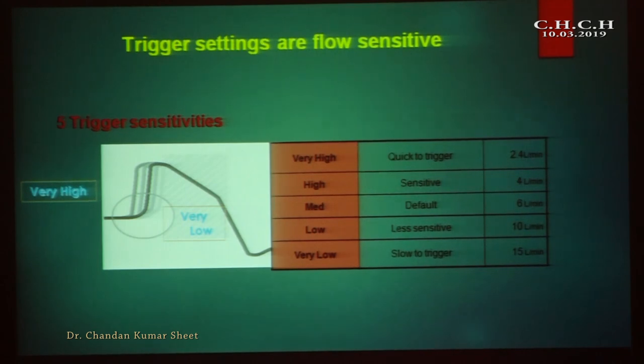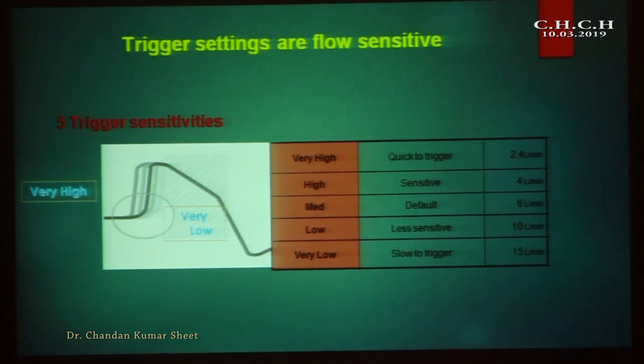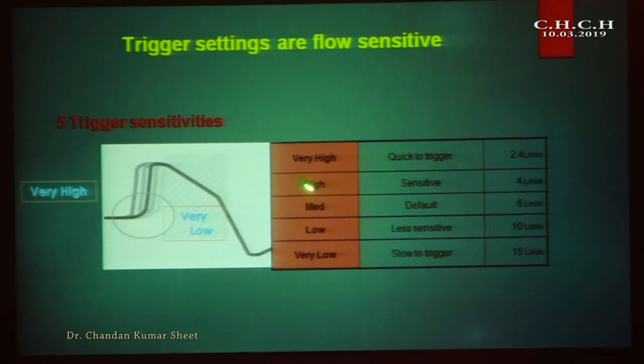We can set trigger sensitivity at five levels: very high, high, medium, low, and very low. At very high trigger sensitivity, the flow required is very low — only 2.4 to 5 liters per minute. At very low trigger sensitivity, the required flow is very high. Patient movement, tube movement, or slight coughing may generate enough flow to trigger the ventilator, leading to asynchrony. By default, trigger sensitivity should be set to medium, which is 6 liters per minute.